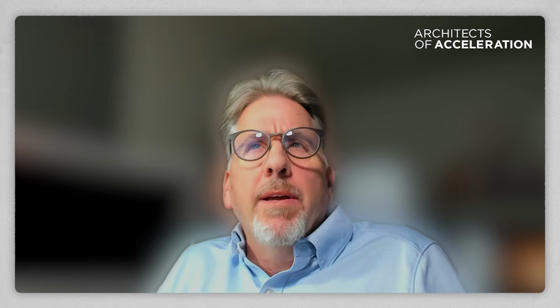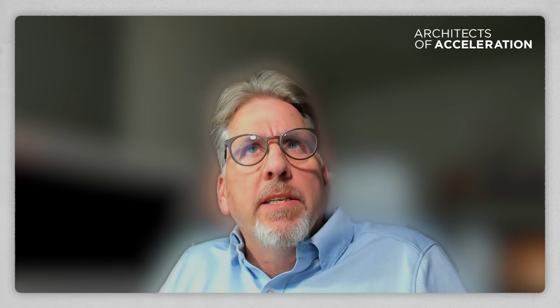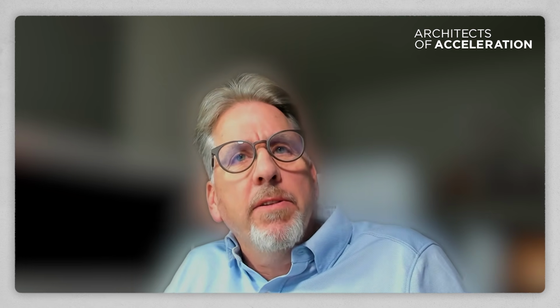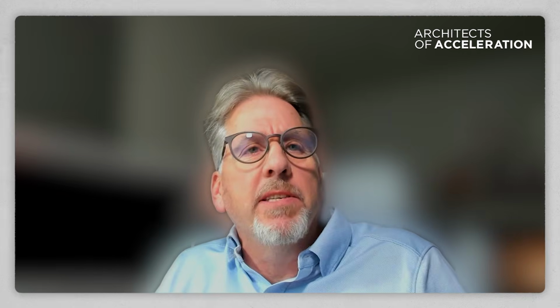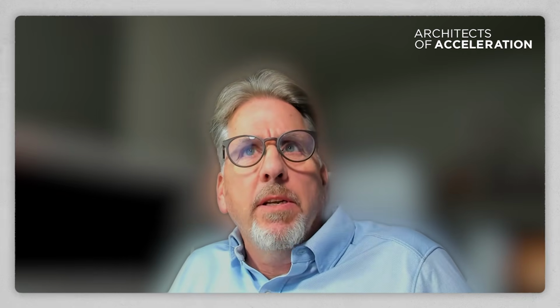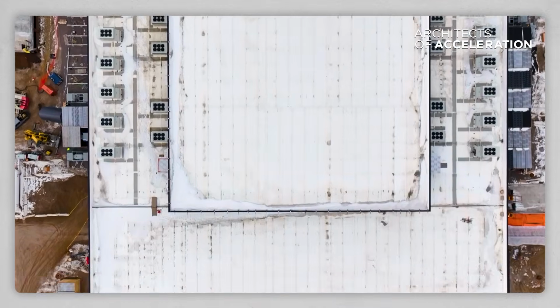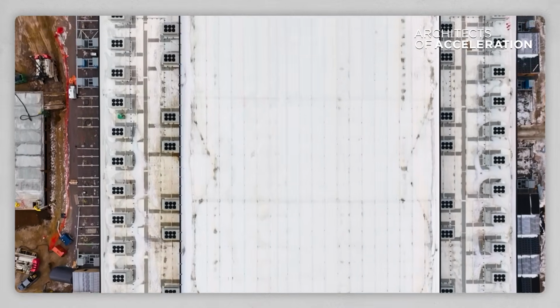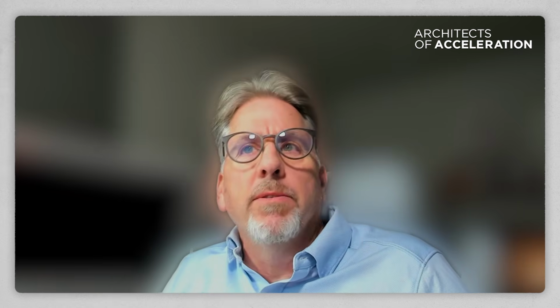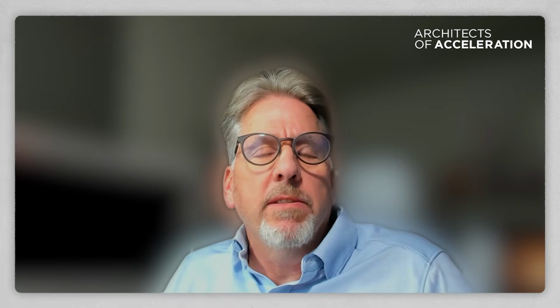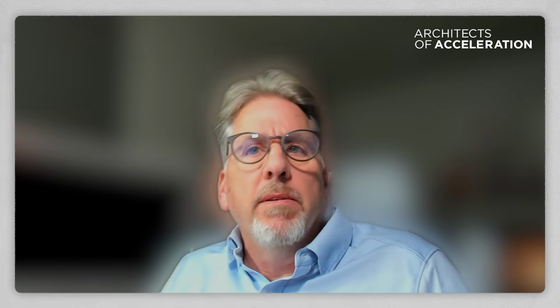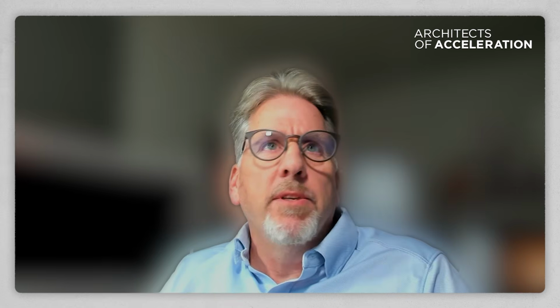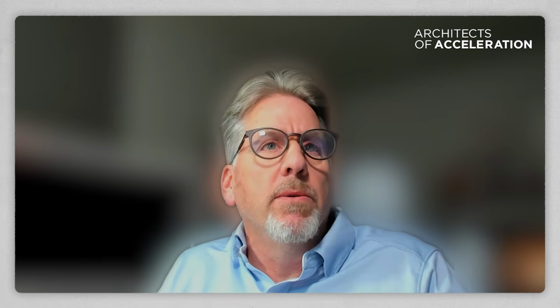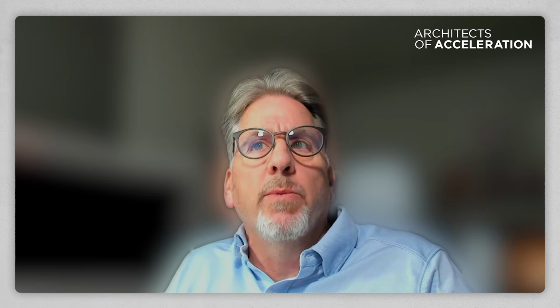Steve, why don't you start, and I'll add from an operational perspective. From the commissioning side, it's not much different from your typical data center. The equipment's pretty much the same. It's the quantity of the equipment, the scale we're building at, that's the biggest difference. So instead of your normal data center where you hit 4, 5, 6 lineups, in the AI world you're hitting 40 lineups in some cases.